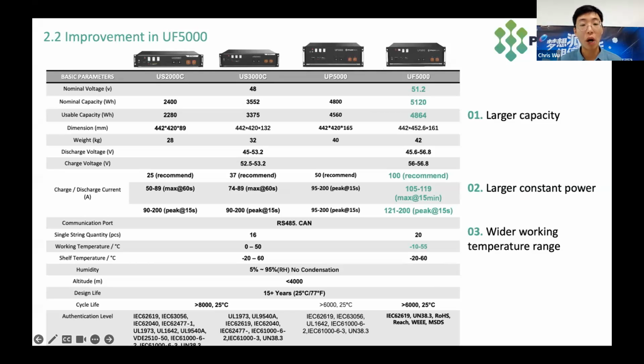As for the communication, all our low voltage batteries share the same communication protocol, so they can support RS485 communication or CAN communication. It depends on the customer inverter. Then it's about the capacity expansion. For our US2000C, 3000C, and UP5000, they can parallel up to 16 in one group. And you can also use an extra device called LV hub to expand up to 6 groups. So there can be 96 batteries in one system. For UF5000, you do not need an extra device, and they can connect in parallel up to 20 pieces in one system. I think that will be quite enough for most residential use.